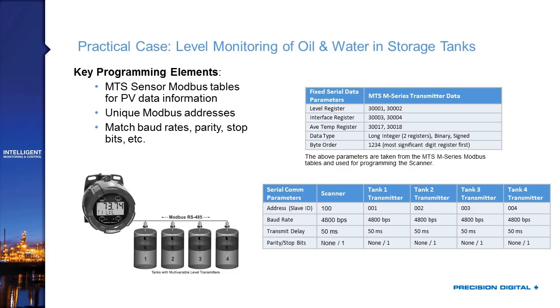Setting up the Modbus scanner: every device gets its own unique address — including the scanner itself, which is set to address 100, while the four tanks are assigned addresses 1, 2, 3, and 4. Those numbers could be anything as long as they're all different. All devices must match their baud rates — everything is matched at 4,800 baud. Transmit delay is left at the factory default of 50 milliseconds since it's not well understood and the system works fine with it. Parity and stop bits are all set to no parity and one stop bit across all devices.